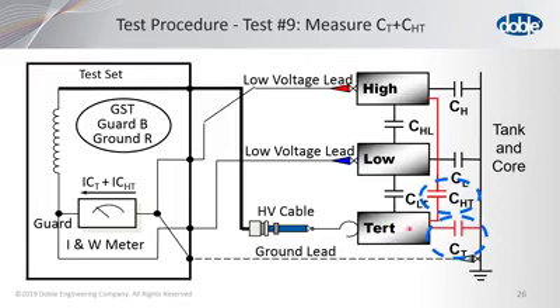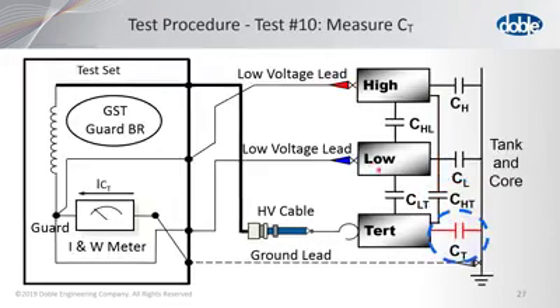Notice that CT goes to ground, and the CHT is grounded by the low voltage lead, so you measure both. One thing I want to point out here is that the low voltage winding in every one of these tests is guarded away. So that low voltage winding disappears to the test. Then we automatically go to test number 10 with the software, right?